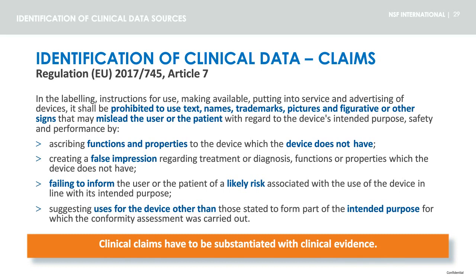So be sure to screen the marketing claims of your device, including website pages and marketing brochures, for clinical claims that need to be covered by clinical data. Clinical claims should also be included in your literature search protocol. Remember that all clinical claims have to be substantiated with clinical evidence.